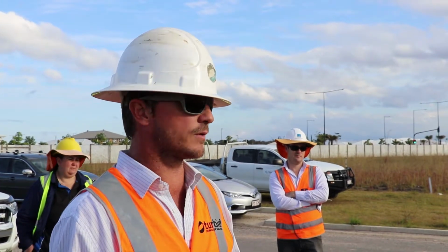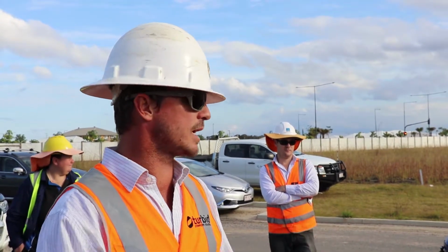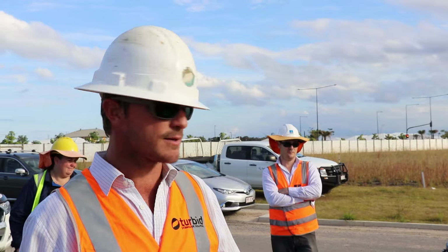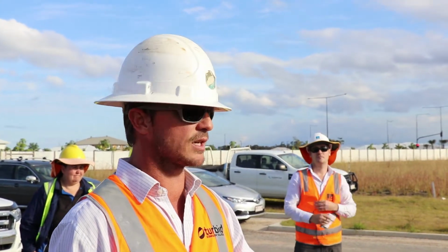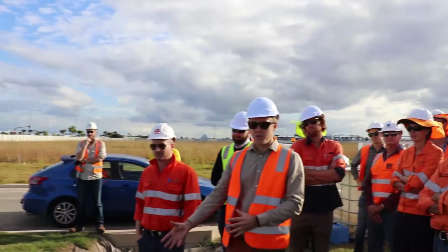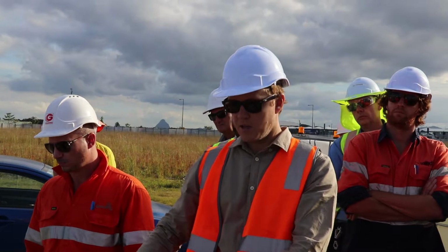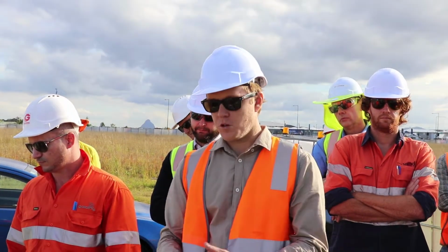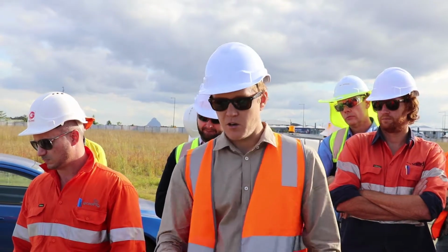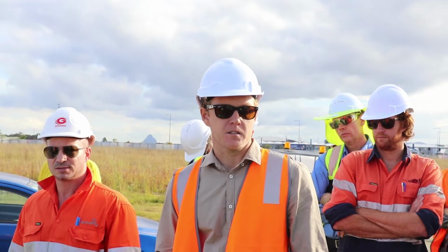So if you're needing a product that needs 300 litres per megalitre for a treatment, say, you're not going to get much out of a system like this. So the smaller the dose rate, to put it simply, the bigger the area this will treat. This is only a small one of these. You can get bigger ones, obviously, but you're going to be limited. If you've got something that needs a really, really high dose rate, you're either going to need lots of these, or you may have to move to a flow activated system.